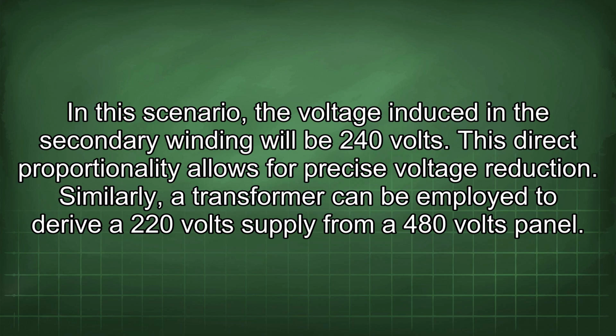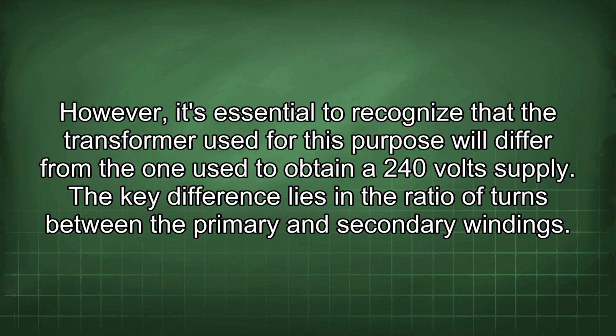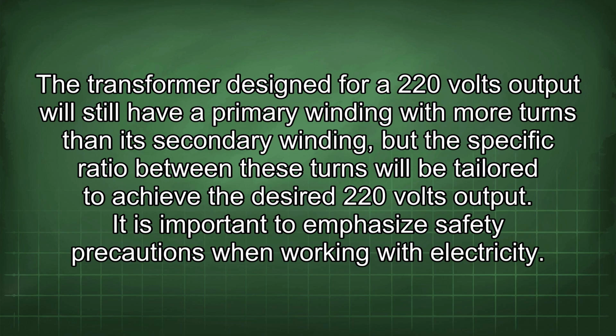Similarly, a transformer can be employed to derive a 220 volt supply from a 480 volt panel. However, it's essential to recognize that the transformer used for this purpose will differ from the one used to obtain a 240 volt supply. The key difference lies in the ratio of turns between the primary and secondary windings. The transformer designed for a 220 volt output will still have a primary winding with more turns than its secondary winding, but the specific ratio between these turns will be tailored to achieve the desired 220 volt output.